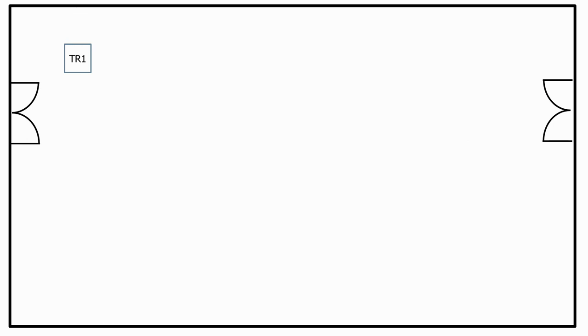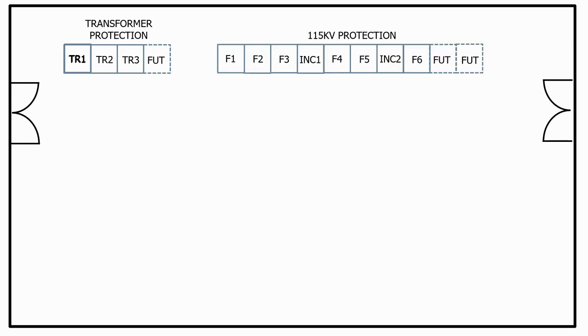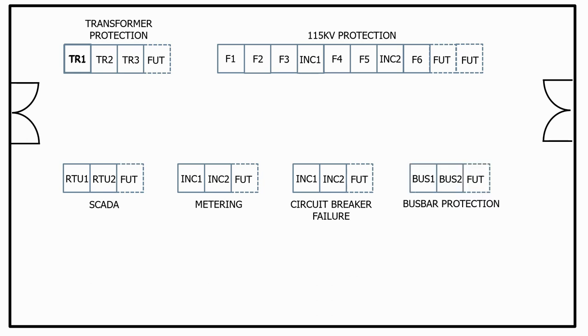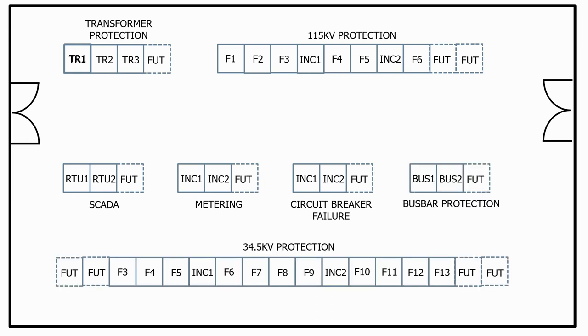We then have to decide how we group the panels together. We normally do this by function. So in this substation we group all of the transformer protection panels together, the 115kV protection panels together, SCADA, metering, circuit breaker failure, bus bar protection, and finally the 34.5kV protection panels. In most substation control rooms you will also find some wall mounted panels such as DC distribution panels and AC distribution panels, which will provide all of the supplies needed for the relay and control panels.